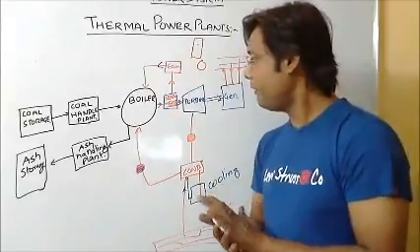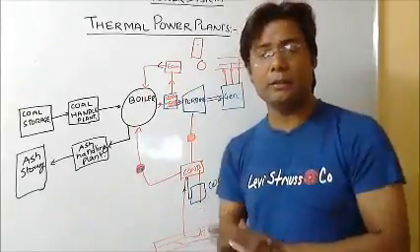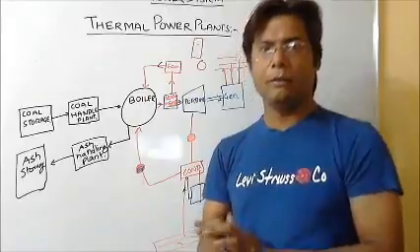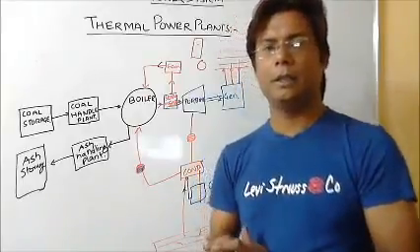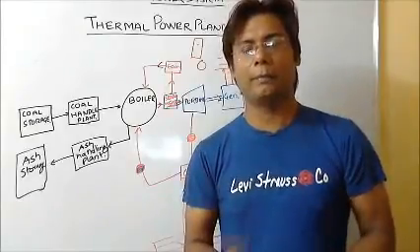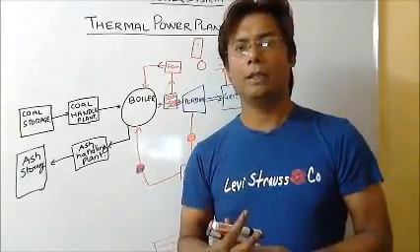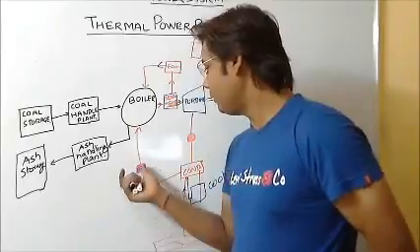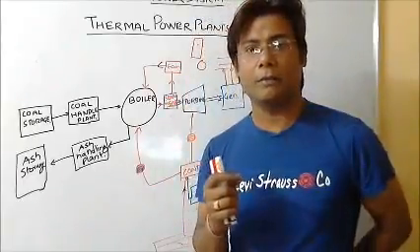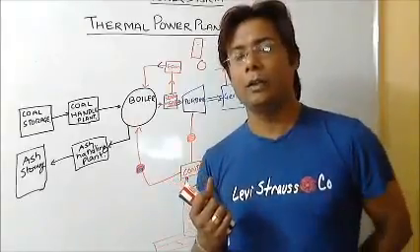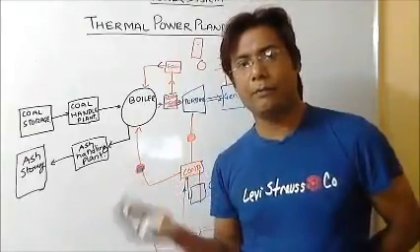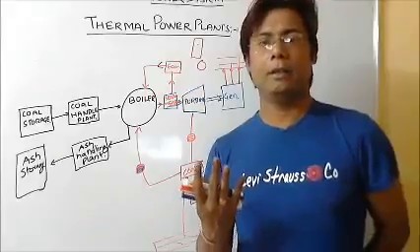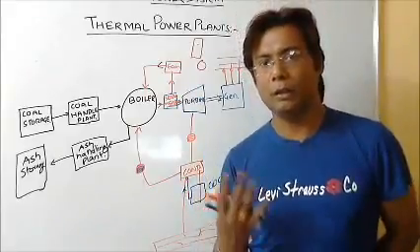So we are using different methods. We are using reheaters also, superheater also, economizer also. There is a slight difference between all those, which almost everybody knows: the superheater raises the heat, the reheater reheats the steam again. The economizer also takes the heat, so that the water flowing here will pass through the economizer first of all, and whatever heat is extracted will be heating the raw water. So when the raw water enters the boiler, it already has some heat, which will ultimately increase the efficiency of the total thermal power station.